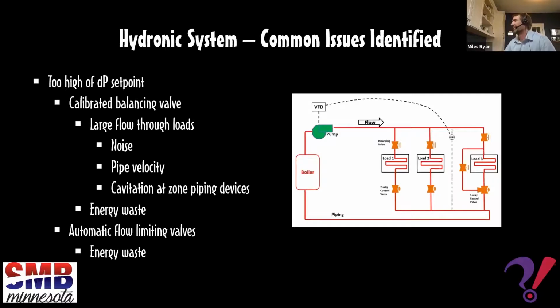I was like, well, we need you to come back because we need to back that set point down to an appropriate value so this pump isn't running at full tilt all year long just to have these auto flow limiting valves throttle back and dissipate that pressure. So he did come back. We landed on a differential pressure set point of 8 pounds that we're operating at now. And in turn, we're not wasting so much pump energy.